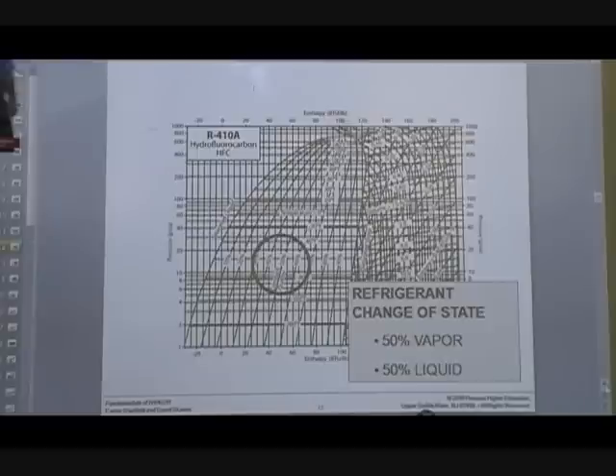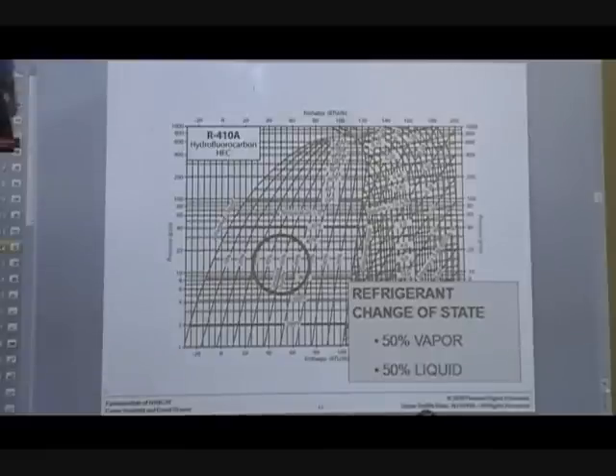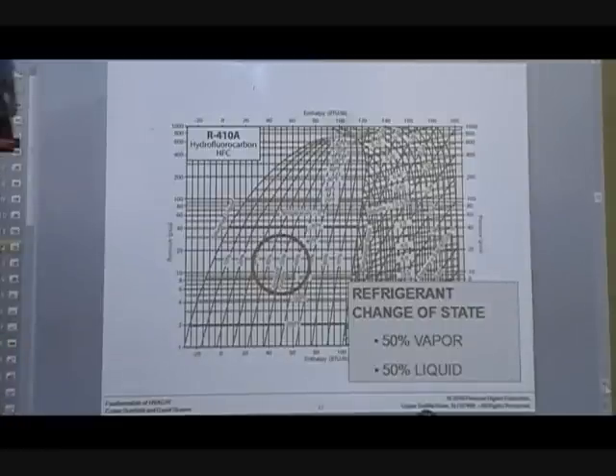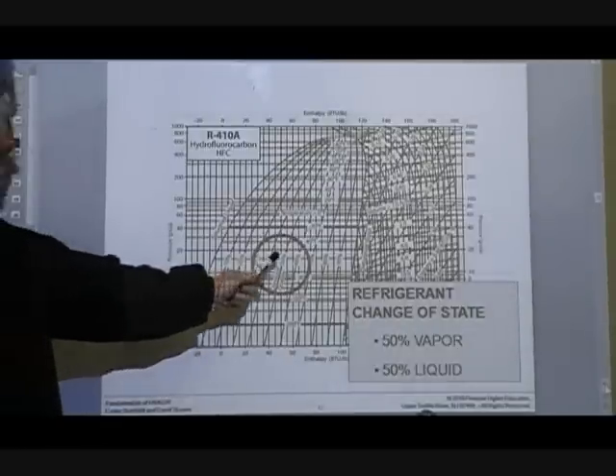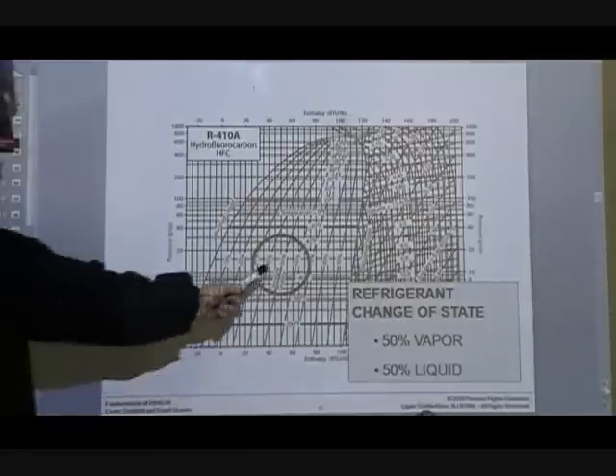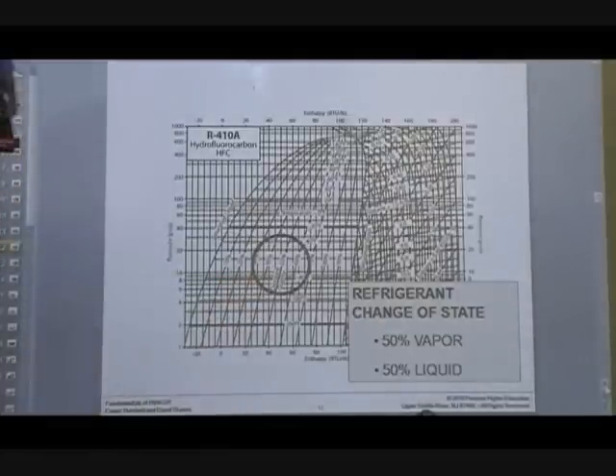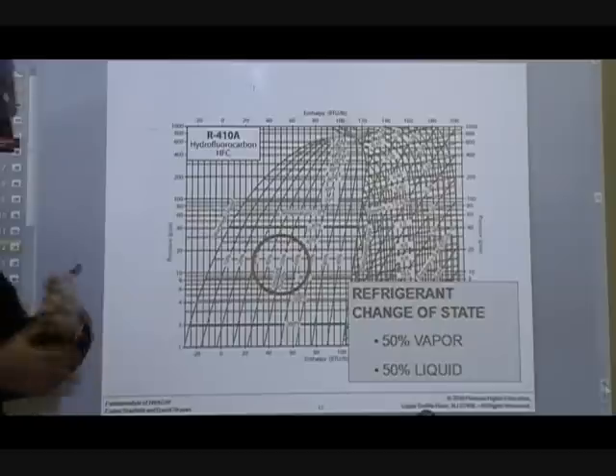50 percent liquid, 50 percent vapor occurs about halfway through your condenser, or you could say halfway through your evaporator — half liquid, half vapor, the job is not done. If you never proceed beyond that point, you've got problems in your system, something's not right. The pressure-enthalpy diagram helps us understand the concept of what's happening inside the system.